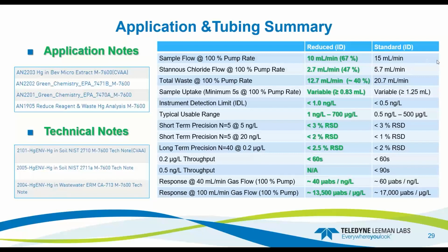Here's a cross section of the differences, which is not huge, but 10 mL to 15, 2.7 to 5.7. But this is the big one right here, that 53% reduction in stannous chloride. And then the total waste is 40% reduction. Variable uptake greater than 0.83 mL per minute, and greater than 1.25 mL per minute at 100% on that flow as well. So the instrument detection limit for sure less than 1, less than 0.5. Typically this is around 0.6 or 0.7.